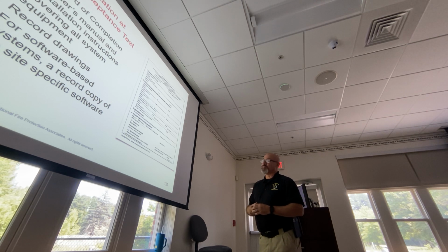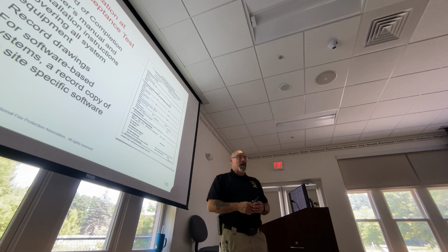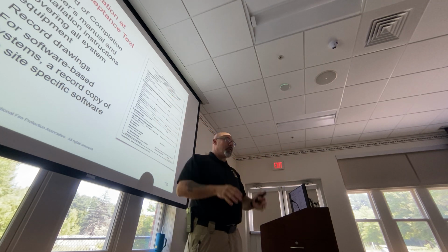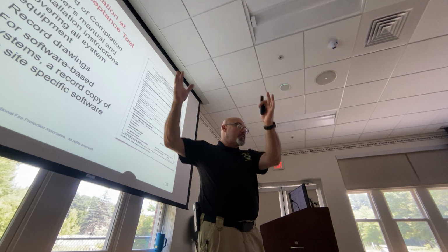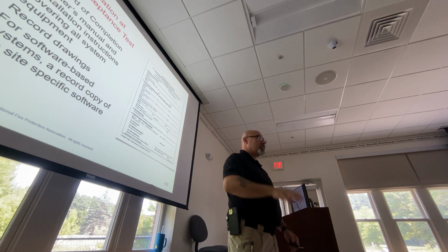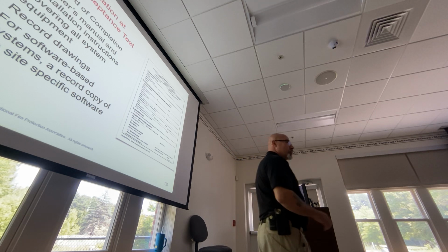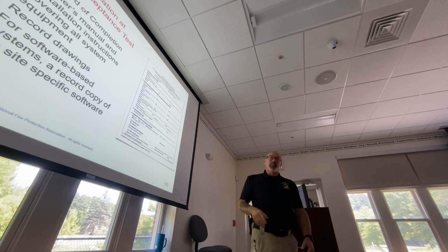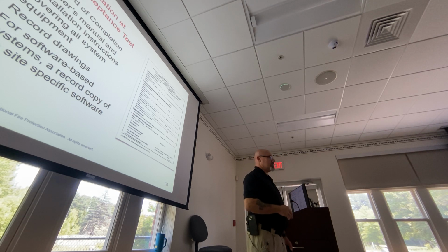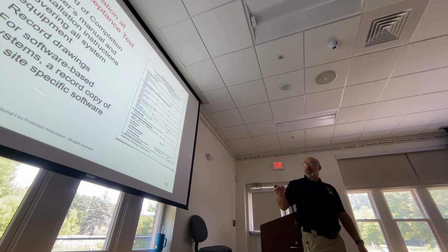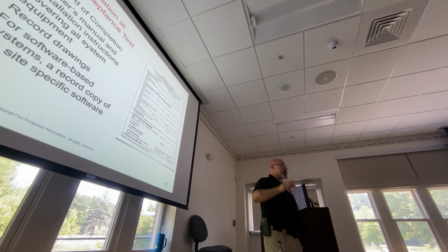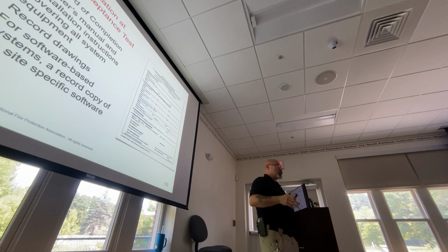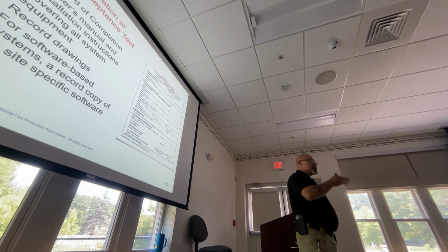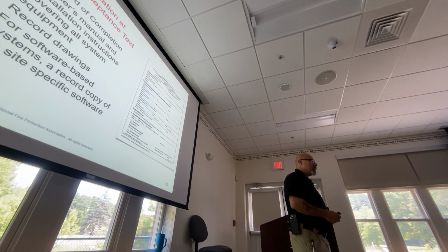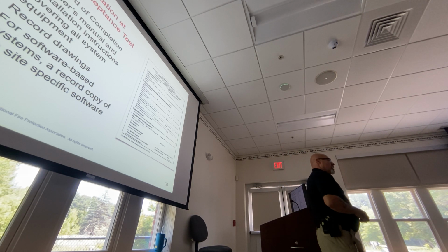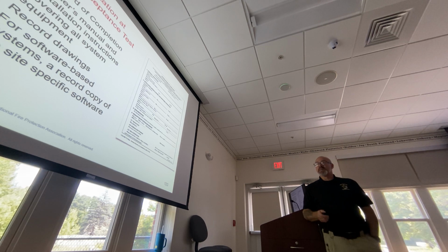That should all stay with the fire alarm. You find a fire alarm system, find the fire alarm panel. Technically, there's supposed to be a box that looks similar to the fire alarm panel next to it that has all the information in it: the record drawings, the certificate of completion, all of the device information that goes along with it, possibly the software-based system records. It's under lock and key in that box. By code, that's supposed to be there. Years and years of inspections have gone by, and that box is not there. We're finding that all the time. But the code says it has to be.